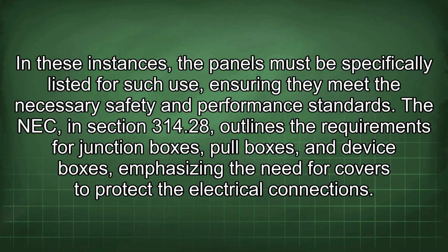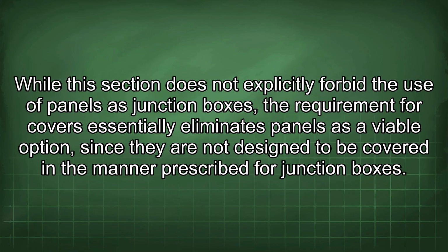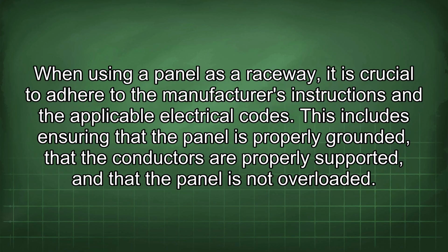The NEC in Section 314.28 outlines the requirements for junction boxes, pull boxes, and device boxes, emphasizing the need for covers to protect the electrical connections. While this section does not explicitly forbid the use of panels as junction boxes, the requirement for covers essentially eliminates panels as a viable option since they are not designed to be covered in the manner prescribed for junction boxes. When using a panel as a raceway, it is crucial to adhere to the manufacturer's instructions and the applicable electrical codes.